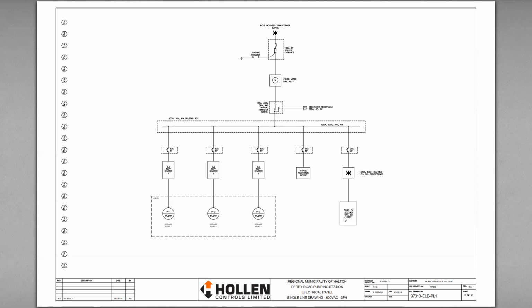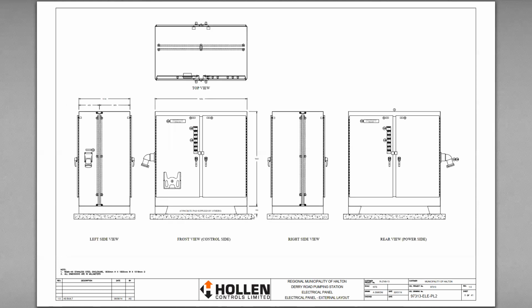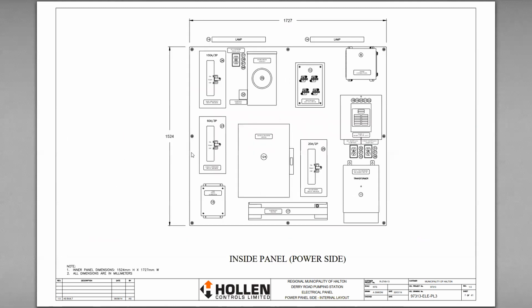Surge protection equipment and a small lighting panel. This pumping station is required to be built without a building. So there's this huge double-sided 4-door stainless steel panel. On this side was the control, and on this side was the high voltage stuff. On the high voltage side, just like an MCC or a building, your main power will come into the meter. There's a manual transfer switch that would switch over to the generator when it was connected in.